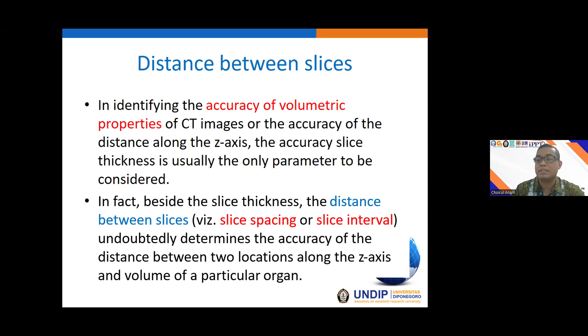Okay, it is the theory, the distance between slices. In identifying the accuracy of the volumetric properties of the CT, there are two parameters: slice thickness and distance between slices, or slice spacing. So it is actually not enough to only guarantee the accuracy of the slice thickness, but we should also have the accuracy of the slice spacing, because these two parameters are very important and affect the accuracy of the three-dimensional images.